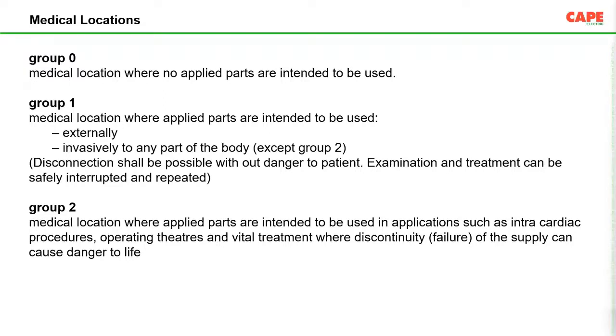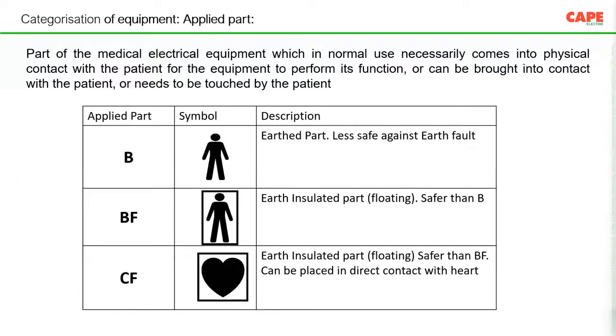So the first point is the medical locations are grouped as per this particular standard into group 0, group 1 and group 2 medical locations. The next is the applied parts. Applied part means the part of that particular medical equipment which finally is connected to the body of a person. So there are earthed parts, earth insulated parts, and earth insulated parts floating.